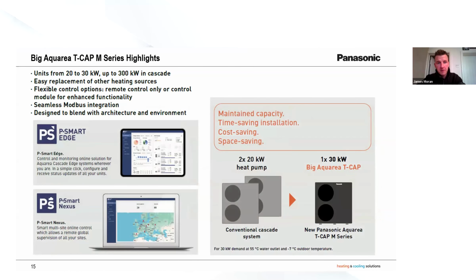Further integration, so if you're wanting to cascade these units, multiple units at the same time, which could be cost saving, space saving and CO2 saving versus multiple gas boilers. To put it in perspective, we had a project recently where we went to site and there were multiple 60 kilowatt boilers in there, and one of them wasn't even being used. So you can imagine when we're looking at sizing and design, there's a 60 kilowatt boiler sat there not being used. So we're talking about efficiency. Design, which we'll touch on later, is really key to getting the right efficiency out of it.